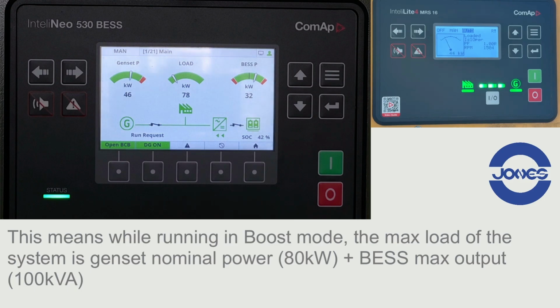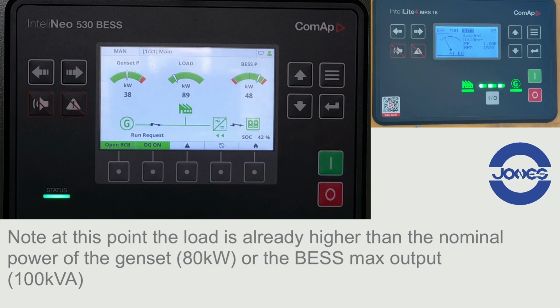This means while running in boost mode, the maximum load of the system is the genset nominal power, which is 80 kilowatts in this case, and the BESS maximum output, which is 100 kVA. Note at this point the load is already higher than the nominal power of the genset, which is 80 kilowatts, or the BESS maximum output of 100 kVA.